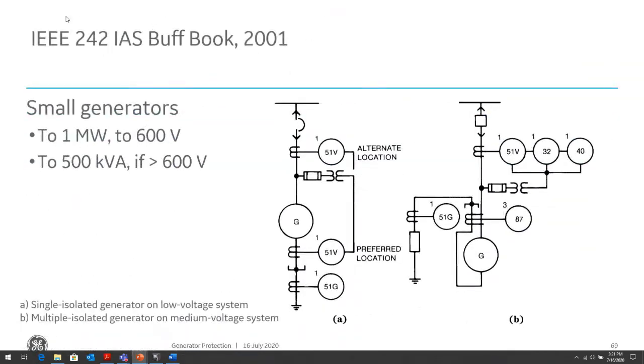Let's take a look at an example from the IEEE 242 IAS book. Again, this refers mostly to industrial generators, small to medium generators, which usually may not have a differential. It's usually a low impedance grounded, high impedance grounded or solidly grounded generator, so fairly straightforward. We can have overcurrent elements. The 51V element is a voltage restraint overcurrent element. If I have a high impedance ground fault somewhere, my current is going to be low, so I want to look at voltage also, to see that the voltage is depressed and tell that there's a fault on that generator.